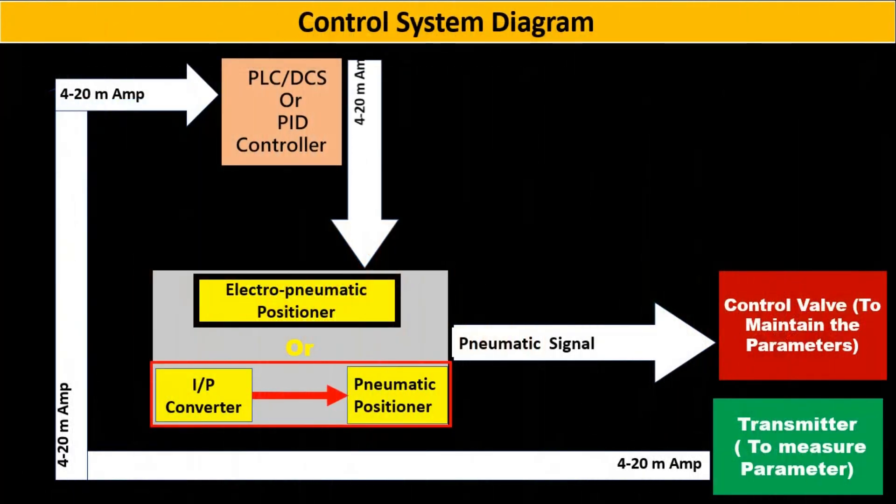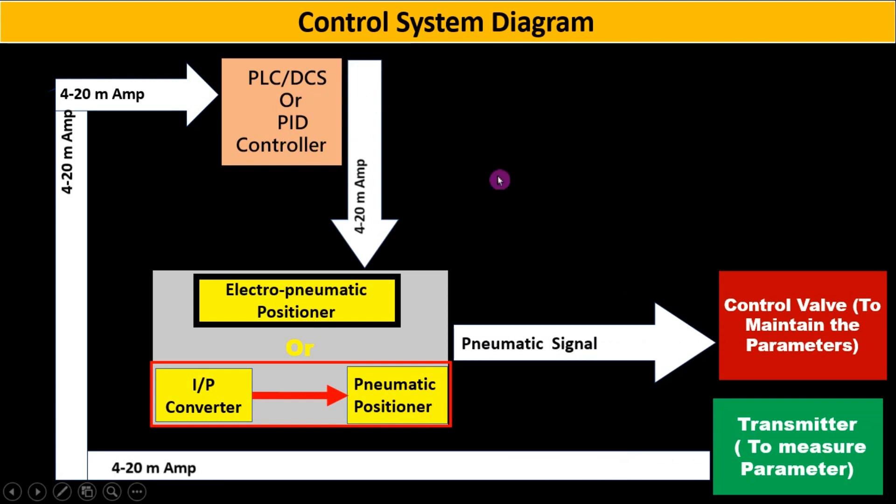Now see the control system diagram. The control system diagram is explained by animation. 4 to 20 mA signal is given by controller. This 4 to 20 mA is provided to electro pneumatic positioner. Sometimes we use I/P converter and pneumatic positioner in place of electro pneumatic positioner. The output of electro pneumatic positioner or pneumatic positioner is a pneumatic signal.